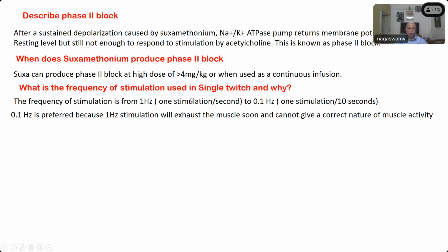And what is the frequency of stimulation used in a single twitch and why? When you use the nerve stimulator to find out the strength of single twitch stimulation, the frequency is from 1 hertz, which is 1 stimulation per second, to 0.1 hertz, which is 1 stimulation every 10 seconds. Normally, you prefer 0.1 hertz because 1 hertz will exhaust the muscle soon and cannot give a correct picture of muscle activity. If you use 1 hertz stimulation, it will just show the strength of the contraction, but using it repeatedly will weaken the muscle or make it tired.